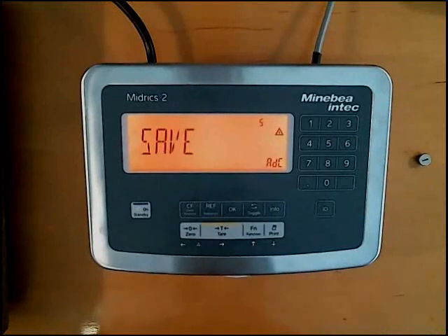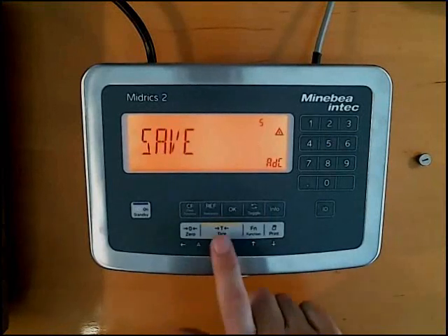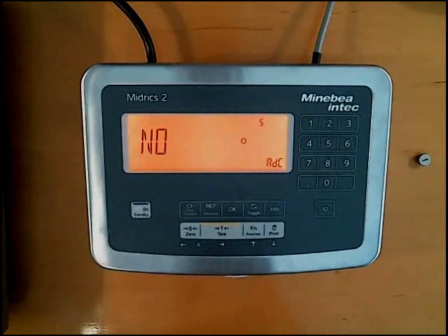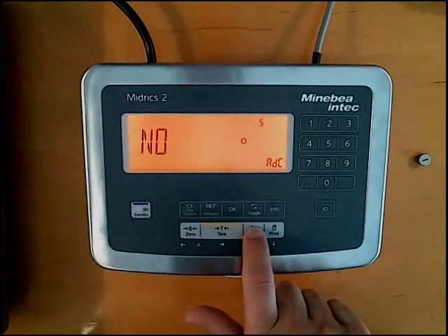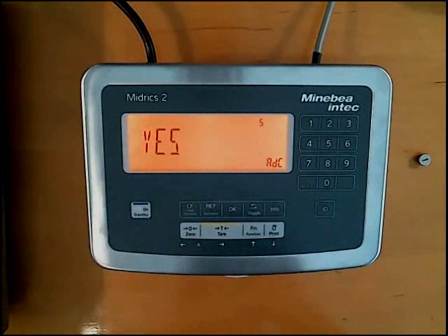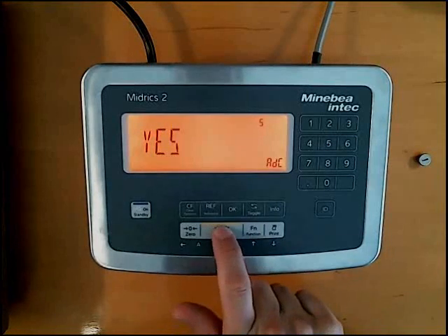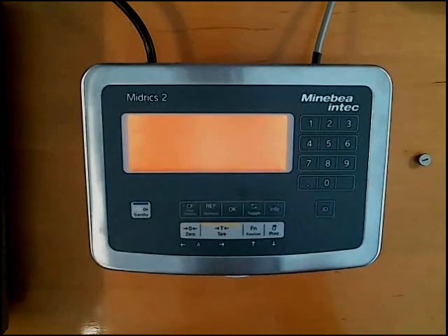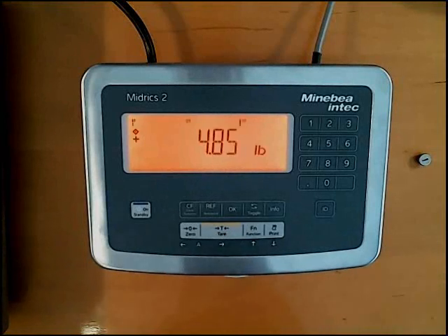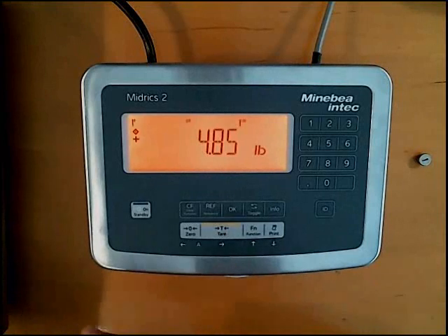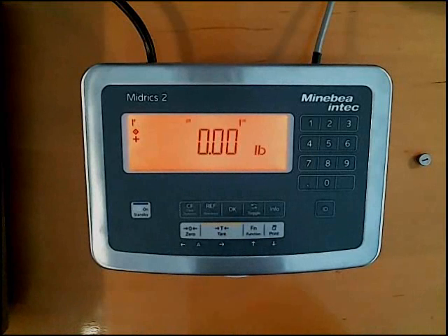You push the tare key, you'll see save. You'll push the tare key again, it'll say no. It'll always say no because you need to press the function key once to have yes displayed, and then press the tare key, and you'll see the unit will go busy for a second. It will flash, the screen goes blank, it will come back on again, and now your A to D converter is set. I had some weights sitting on my scale platform while I was setting up the A to D, but that's not a problem. See how it just went right back to 0. So now your A to D is set up.